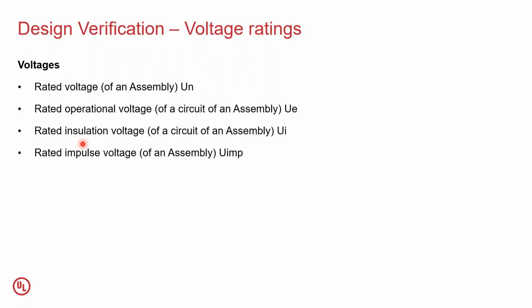Then you have the rated insulation voltage, also called Ui, which is very important for us to perform the dielectric test. Then the rated impulse voltage. Depending on where the installation happens, all these ratings have to be declared by the manufacturer in consultation with the specifier.